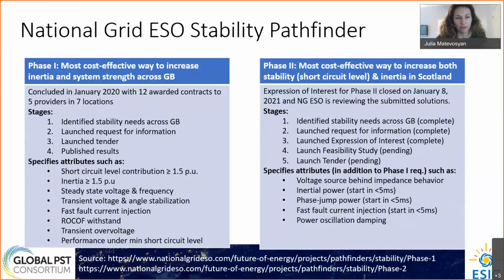The main features they were looking for are short circuit level contribution, inertia contribution, and then steady state voltage and frequency support, transient voltage and angle stabilization, fast fault current injection, relatively high rate of change of frequency withstand, transient overvoltage, and they were also asking for performance under a certain level of existing system strength so that the plant doesn't trip.